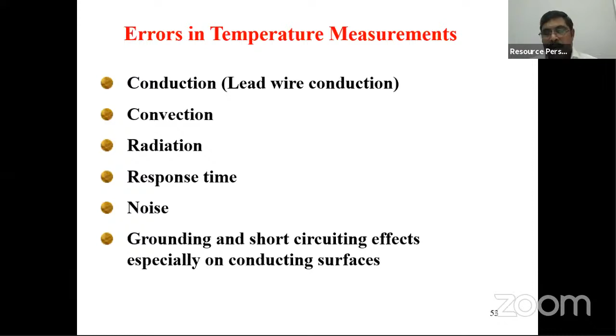You must consider all these things. Particularly when using a thermocouple, make sure there is no lead wire conduction loss. When the thermocouple faces a cold wall, there will be a radiation error, so in that case we need to use what is called a radiation shield. This is very important, and you must have this basic idea when going for temperature measurement.